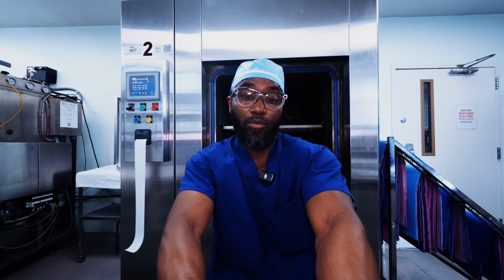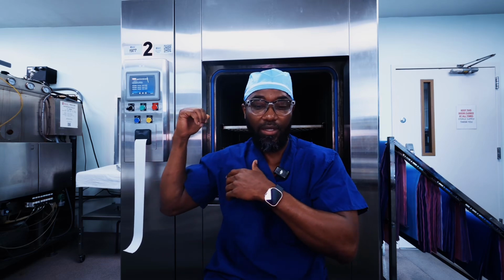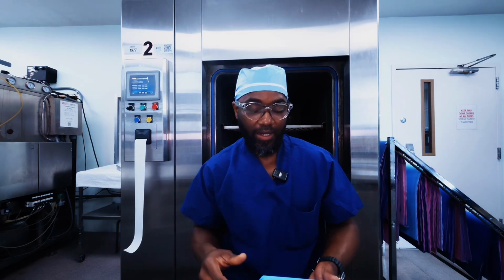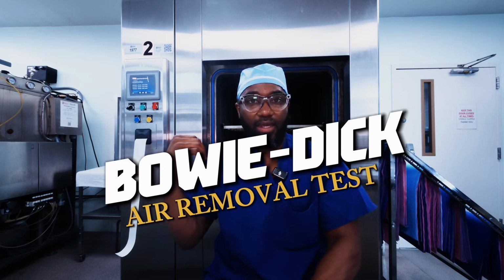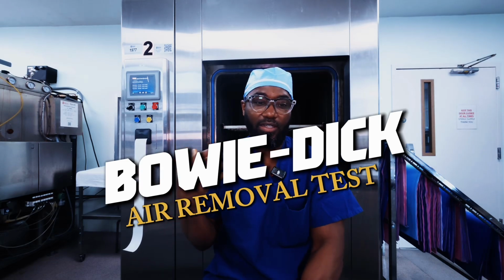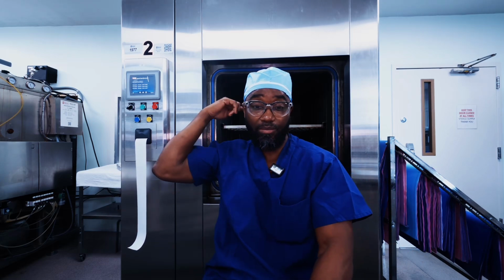For my location, we use steam as a sterilant for most of our surgical instruments. In order to test the efficacy of this machine behind me, it has to go through 3 qualification tests during the sterilization cycle. Before we start our day using this machine, it has to go through a process called a Bowie-Dick air removal test. It is a dynamic air removal steam sterilizer, and before it sterilizes any instrument, it has to be in a vacuum that is free of air. It means that there is no air present in this chamber behind me.